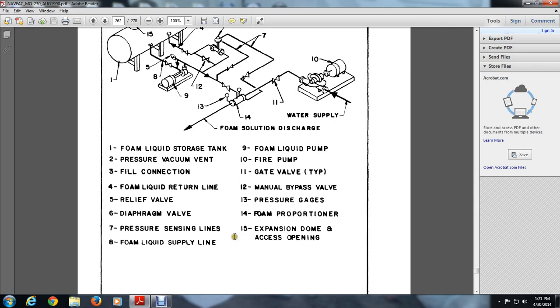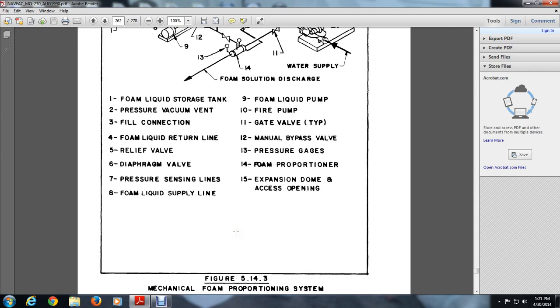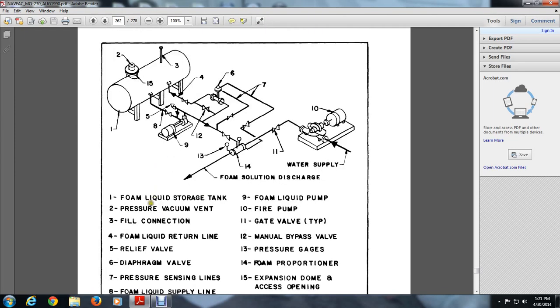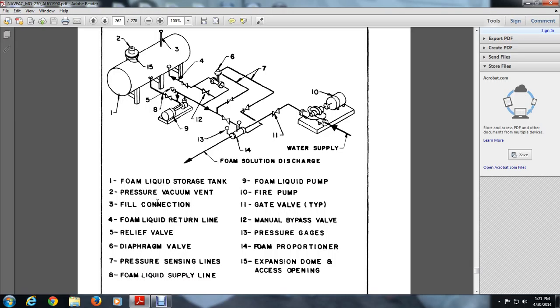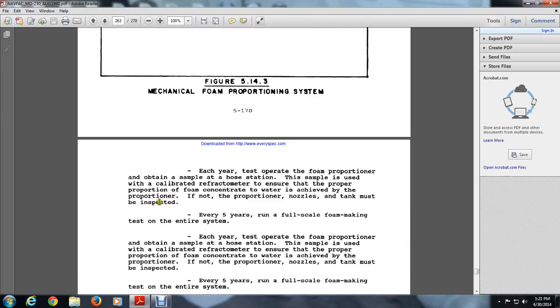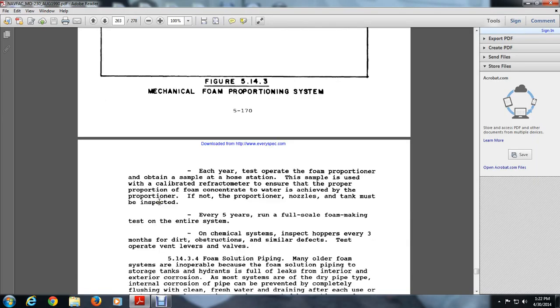Here what you see is a mechanical foam proportioning system, showing: 1, the foam liquid storage tank; 2, the pressure vacuum vent; 3, the fill connection; 4, the foam liquid return line; 5, the relief valve; 6, the diaphragm valve; 7, pressure sensing lines; 8, the foam liquid supply line; 9, the foam liquid pump; 10, fire pump; 11, gate valve type; 12, manual bypass valve; 13, pressure gauges; 14, foam proportioner; 15, expansion dome and access opening.